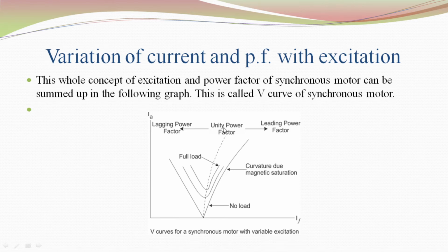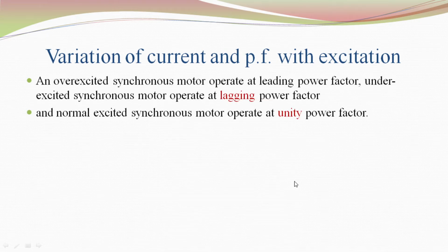Here you can see at no load we are getting a graph like this, and this is at full load. This is at unity power factor in the middle, and here on the right side we can see leading power factor, and the left side is lagging power factor. An overexcited synchronous motor will operate at leading power factor, an under-excited synchronous motor operates at lagging power factor, and a normally excited synchronous motor will operate at unity power factor.